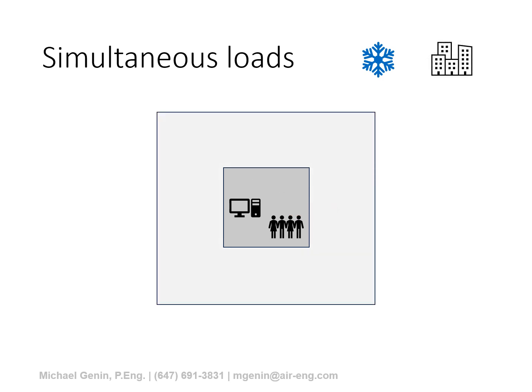So now let's think of a larger building, such as an office tower or shopping mall. We'll have an interior zone, which is shown by the dark gray square, and this might have people and computers and lights, again generating heat. And then we're going to have a zone around the perimeter. And just like before, it's very cold outside, so we will have heat transfer from this perimeter zone to the outside. So to make up that heat transfer, this zone must be in heating mode. We have to be adding heat to the perimeter in order to offset the heat loss through the envelope of the building. However, on the inside of the building, in the core zone, the computers, people, and light bulbs are generating too much heat, and where I've shown this orange X, there is no heat transfer from the core zone to the perimeter zone.